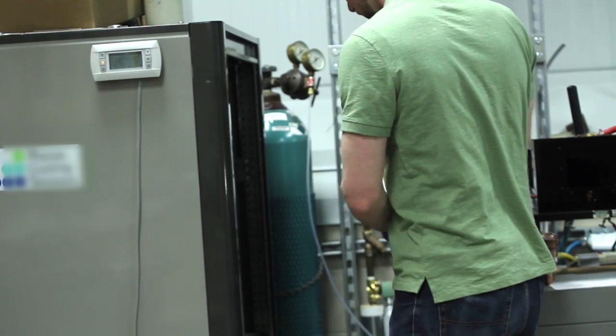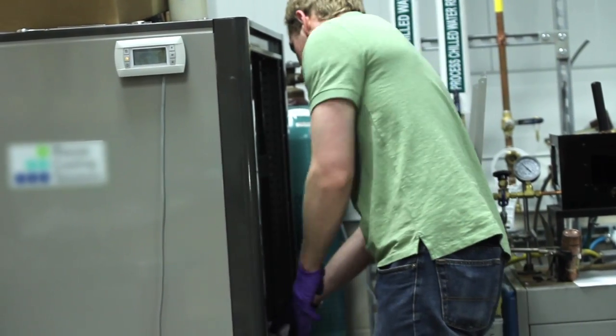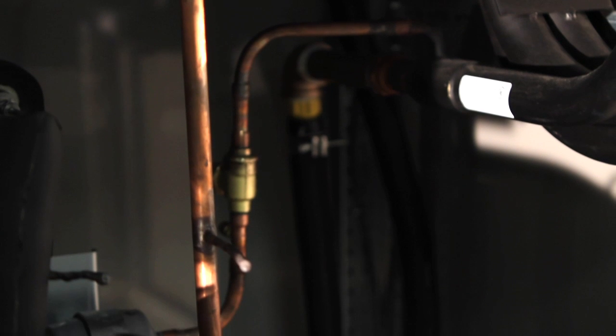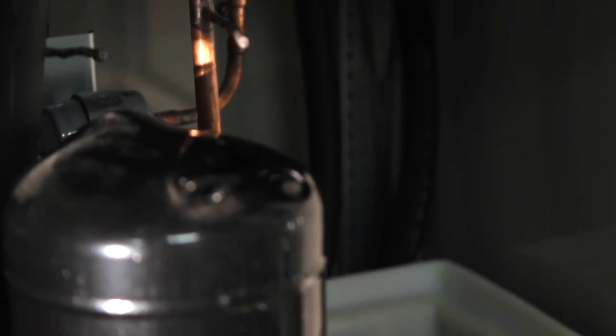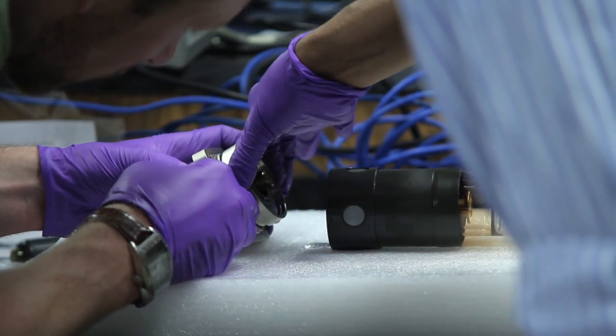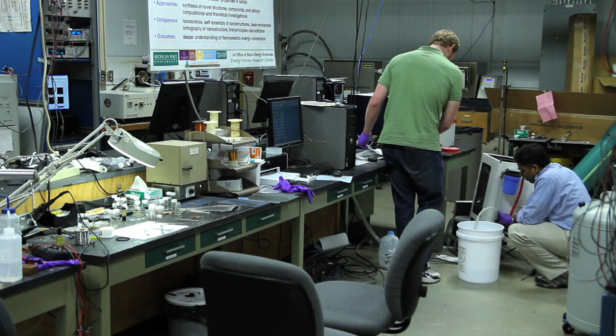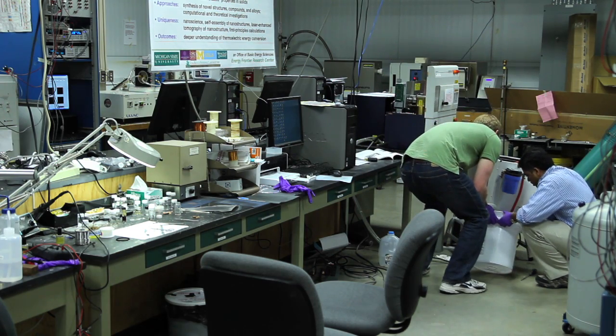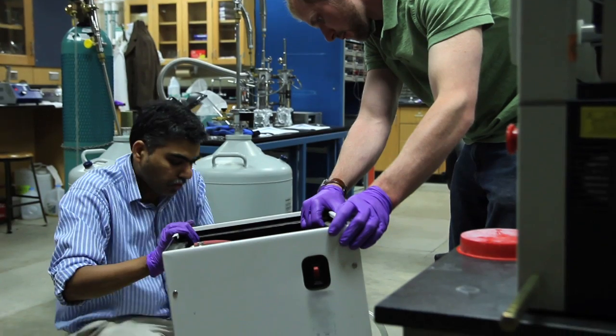The unfortunate consequence of that is that water can pick up debris, corrosive products, etc., as it's used over and over. In the large chiller, we did have a problem with corrosion. When they installed the system, they used some type of ferrous piping, and they just used regular tap water. Before we moved into the lab, that tap water sat in the pipes for several weeks, so when we got here, there was a thick black sludge at the bottom of the chiller tank. We had to flush the system with regular water, and that solved the problem temporarily.